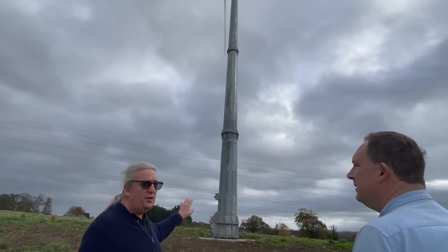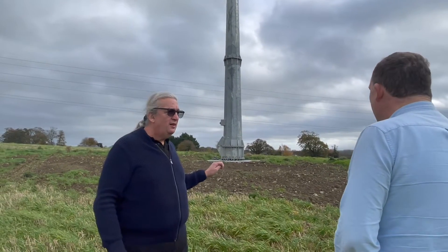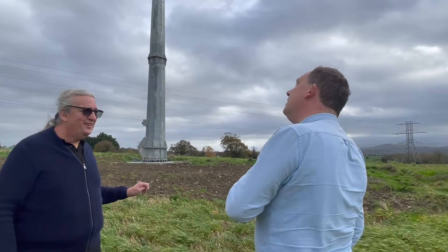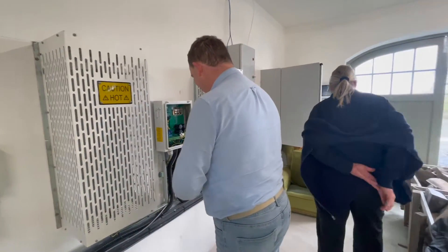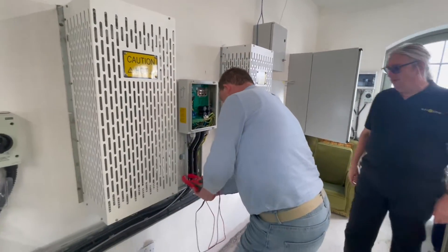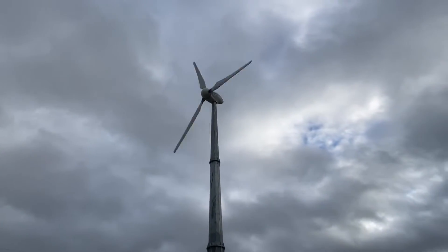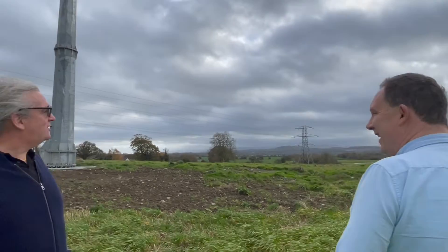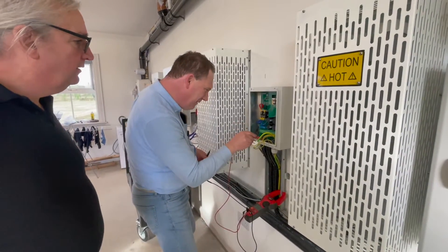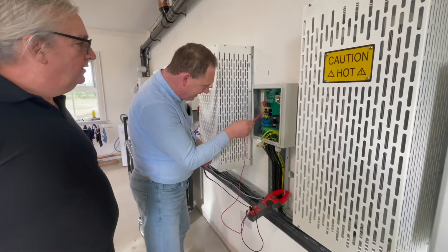So what is the sensor phase here? What voltage? In AC. There seems to be a little bit of excess heat there still, which there shouldn't be. Did you show the power? I just wanted to measure. So we have these are our three phases coming in — what we call our wild AC — coming in here. And that goes straight into this three-phase bridge.